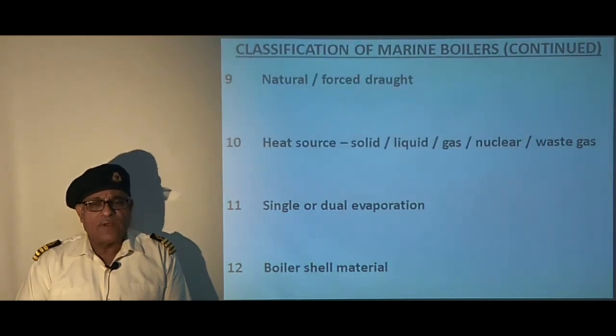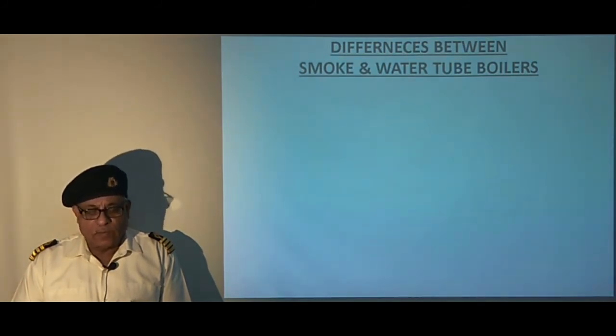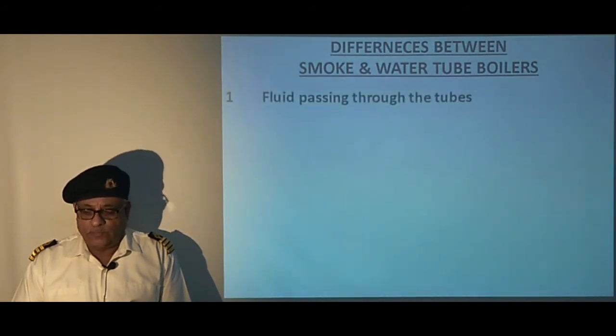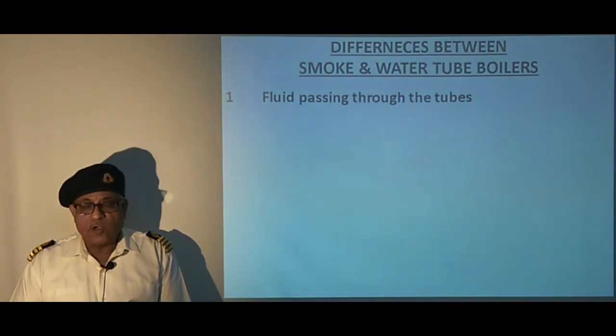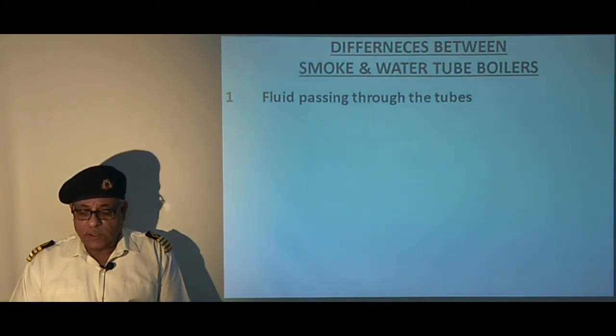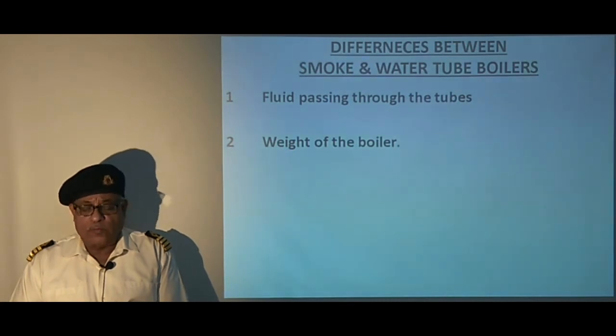Now we will see the differences between smoke tube and water tube boilers. First, regarding fluid passing through the tubes: smoke tube boilers carry smoke or flue gases in the tubes which heat up the surrounding water, whereas water tube boilers carry water and steam in the tubes which are heated by the flue gases flowing over the tubes. Regarding weight, the smoke tube boiler is three times heavier for the same heating surface area, whereas the water tube boiler is lighter, resulting in a reduction in dead weight.